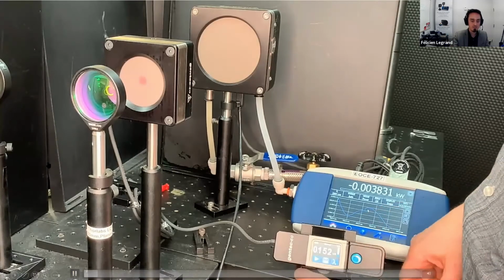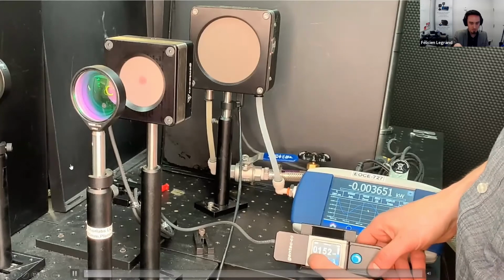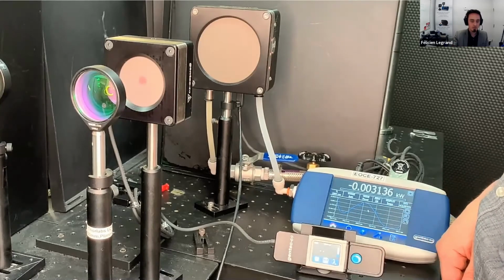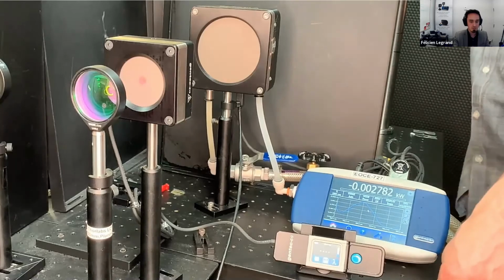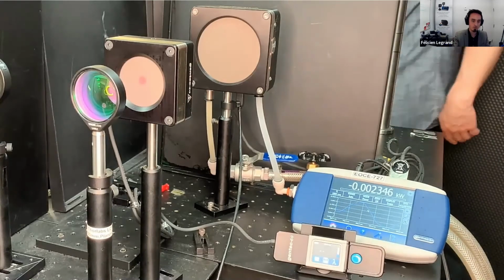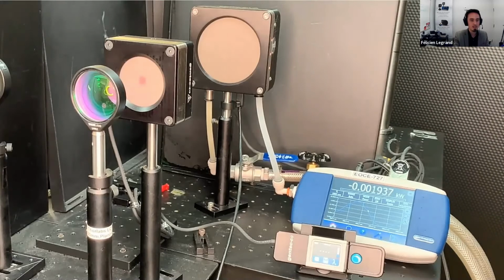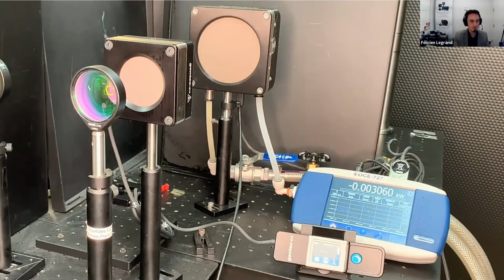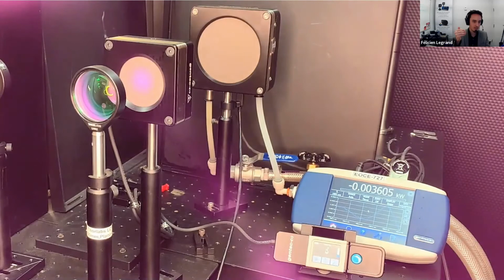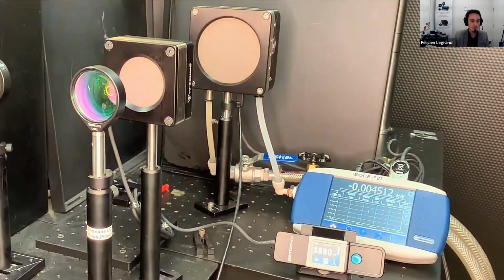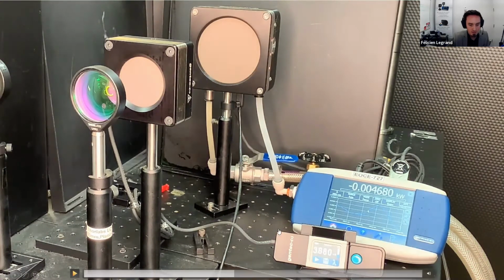Simply press play on the monitor that you see in the bottom right corner. It will wait for the beam to heat up the surface. It's a really powerful laser, so we get out of the way and turn on the laser when it's safe to do so. You will see some back reflection; the camera is capturing some purplish colors. Then after 5 seconds, what you see is a 3.88 kilowatt measurement. It's traceable, plus or minus 5% accuracy, absolute measurement. So that was done during a 5 second quick check.